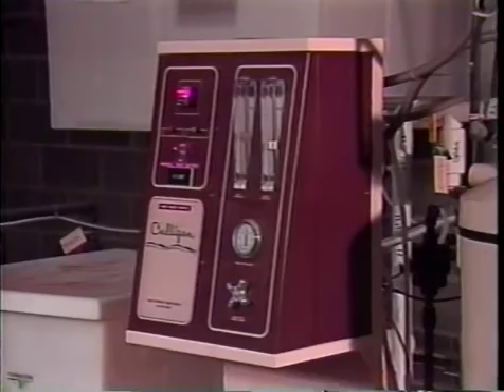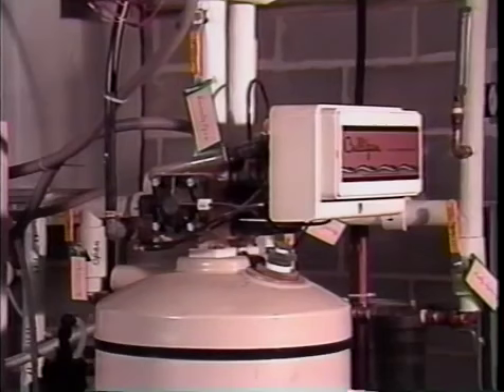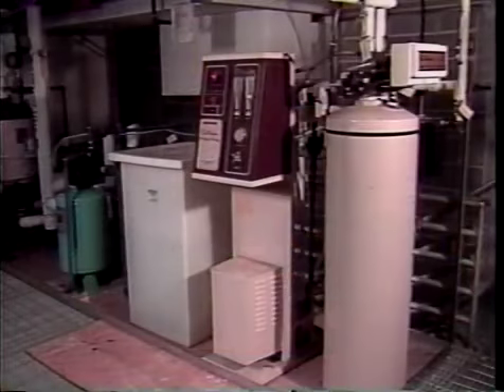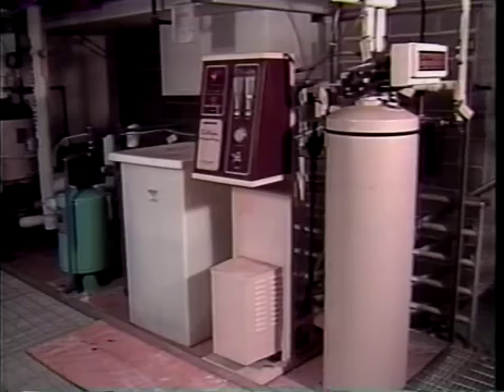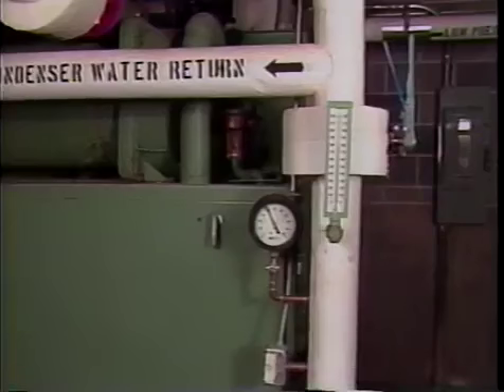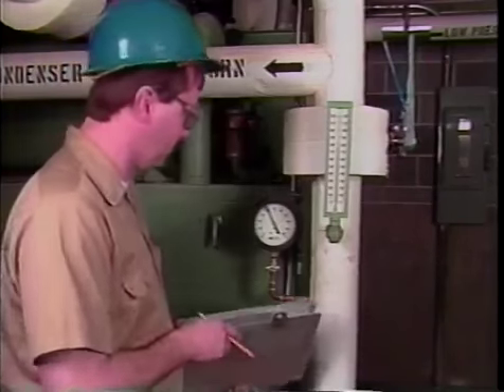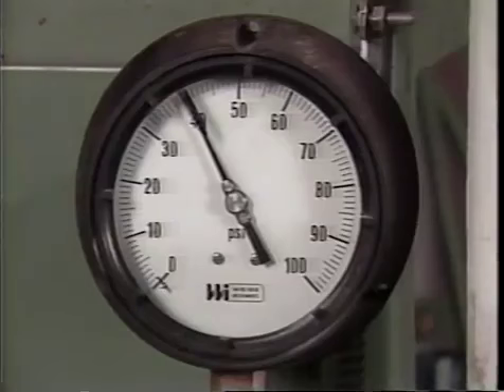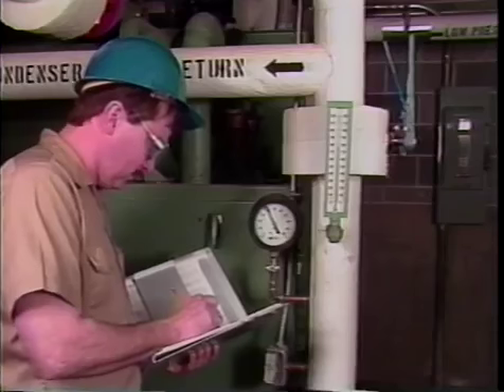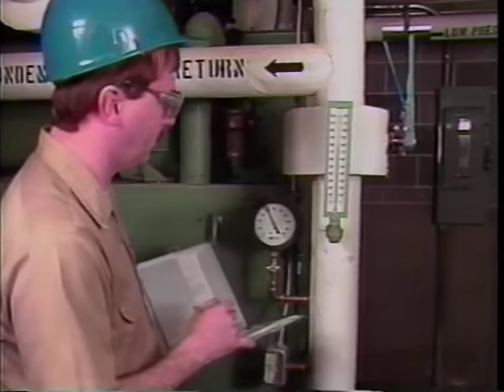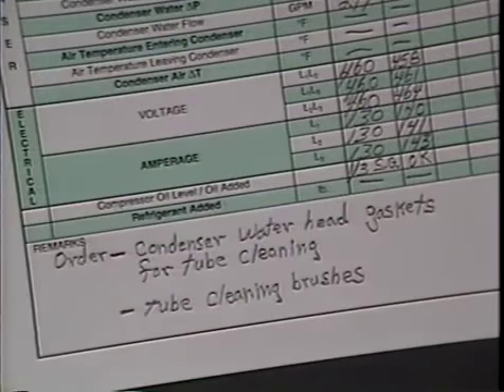Proper treatment of cooling tower water is essential, but even with the best treatment, cleaning of the condenser tubes will be necessary from time to time, as with the once-through systems. A record should be maintained so that the fouling trend is charted and cleaning and water treatment can be scheduled. The logical place for this record is in the maintenance log. And of course, any other maintenance work, parts replacement, or any other work that affects system performance should be documented in the log so that the condition of the system is always known.